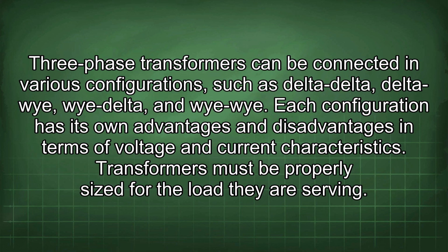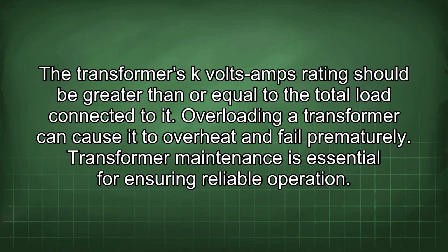Transformers must be properly sized for the load they are serving. The transformer's kVA rating should be greater than or equal to the total load connected to it. Overloading a transformer can cause it to overheat and fail prematurely.